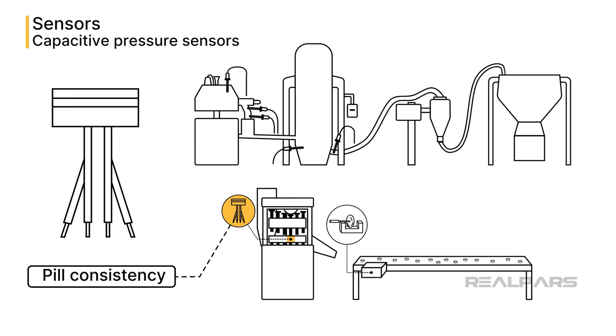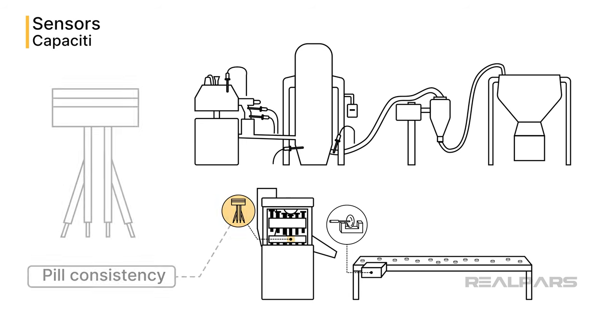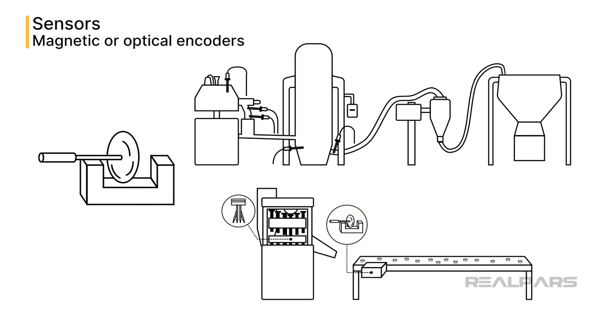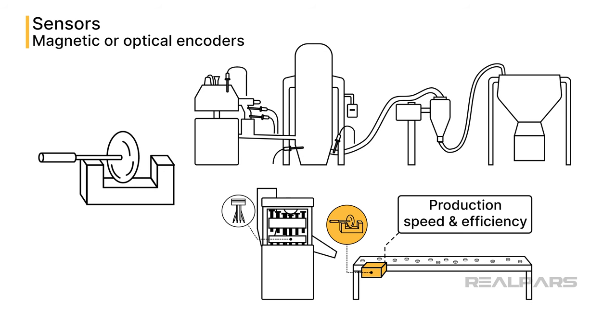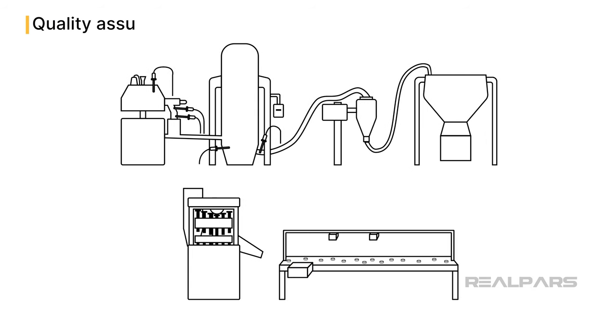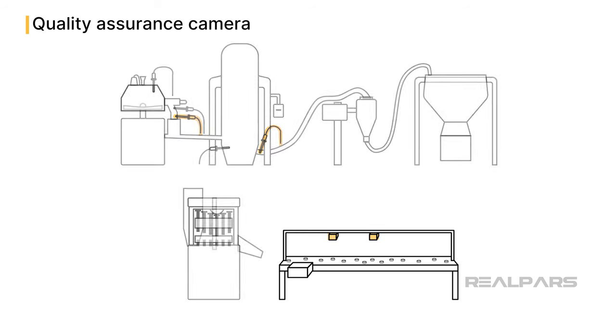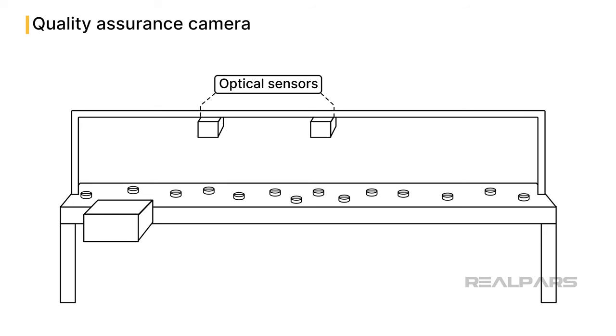Capacitive pressure sensors are commonly used for monitoring pill compaction in the tablet press. The correct pressure ensures that each pill has uniform consistency and does not break apart easily. Magnetic or optical encoders are installed on the product conveyor to monitor belt speed. The rate at which pills are delivered to the packaging line can affect production speed and efficiency. Also of importance are optical sensors that can provide visual evidence of product quality. These cameras are the eyes of the operation.